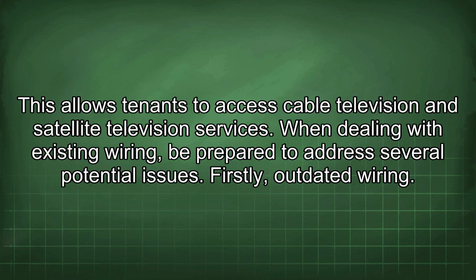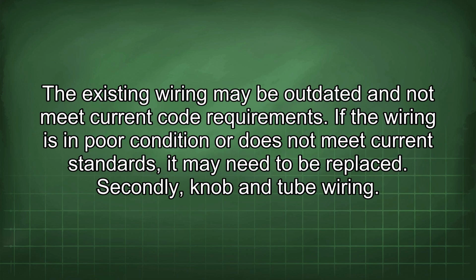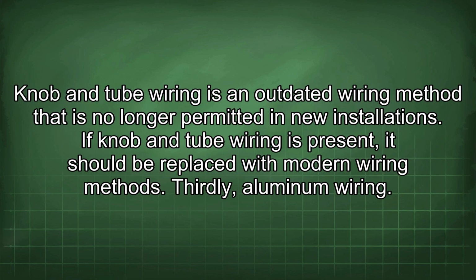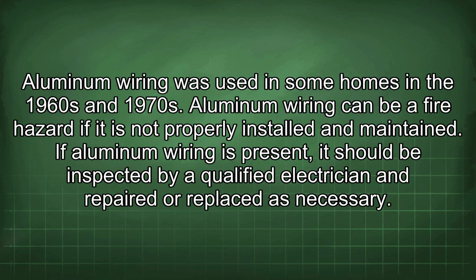Firstly, outdated wiring. The existing wiring may be outdated and not meet current code requirements. If the wiring is in poor condition or does not meet current standards, it may need to be replaced. Secondly, knob and tube wiring. Knob and tube wiring is an outdated wiring method that is no longer permitted in new installations. If knob and tube wiring is present, it should be replaced with modern wiring methods. Thirdly, aluminum wiring. Aluminum wiring was used in some homes in the 1960s and 1970s. Aluminum wiring can be a fire hazard if it is not properly installed and maintained. If aluminum wiring is present, it should be inspected by a qualified electrician and repaired or replaced as necessary.